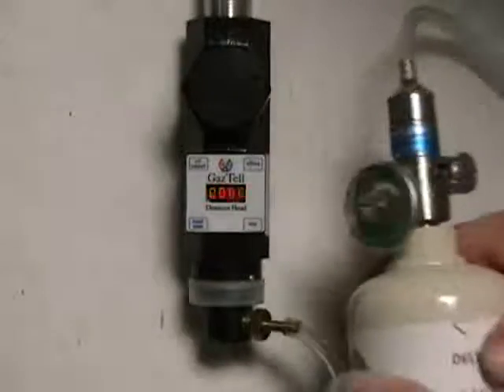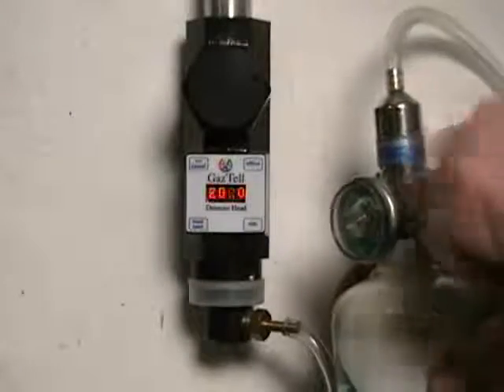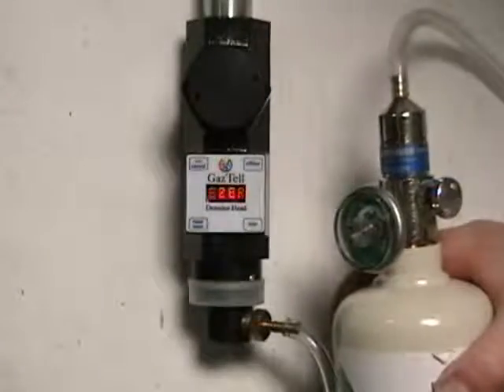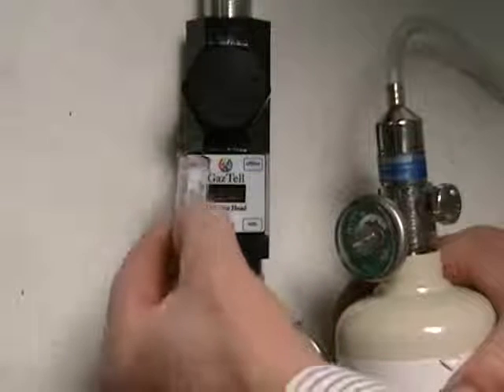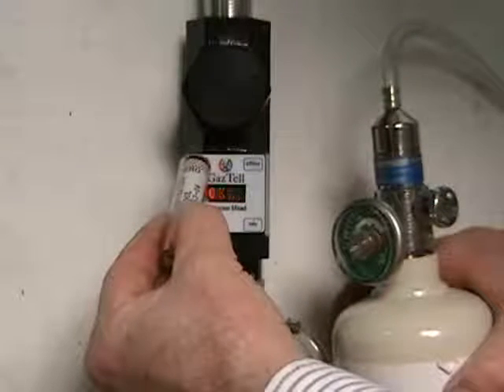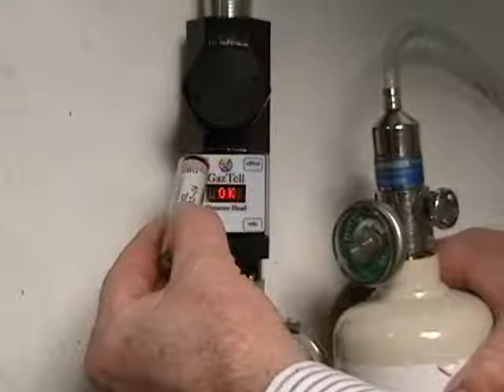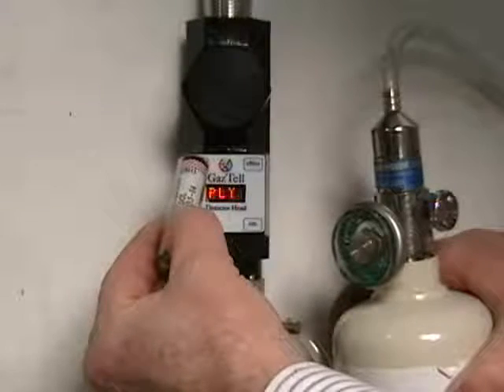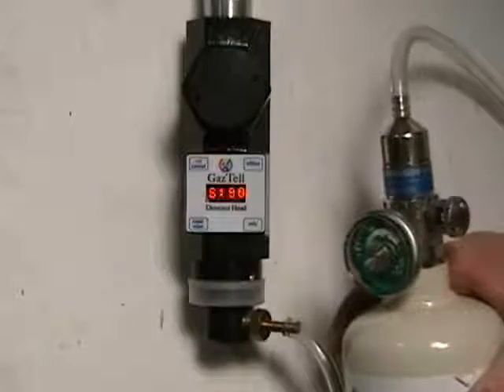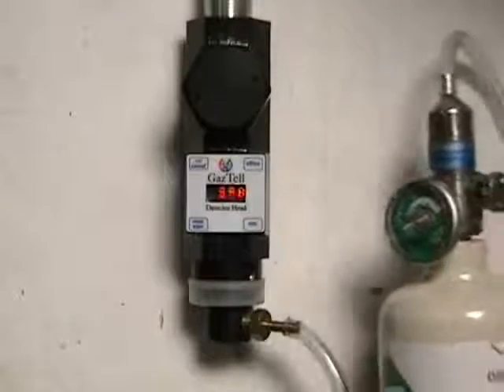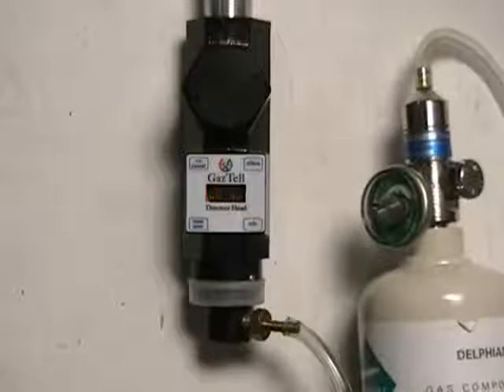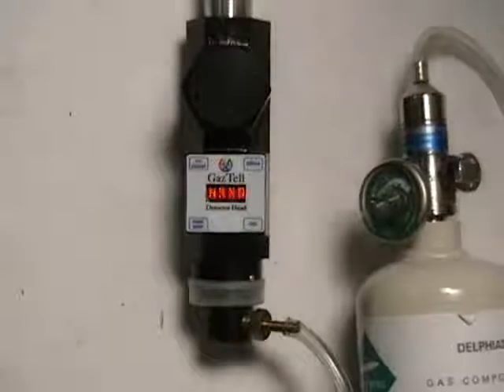To start span calibration, connect your span gas to the calibration cup and turn on the gas regulator valve. Hold the red end of the calibrator over the cal mark for 5 seconds. The display will scroll Apply Span Gas or Spanning if the sensor recognizes that the gas is being applied. The spanning sequence typically takes about 30 to 40 seconds.